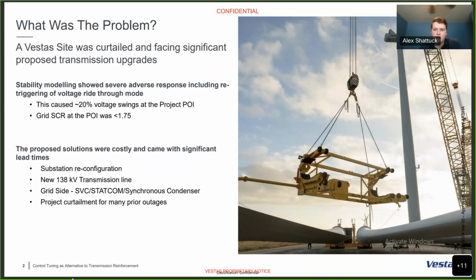The worst case, which no generator owner wants to see, is project curtailment. Basically, for any prior outage, any first level contingency that would cause the N-1/N-1 or cause the adverse response, they're going to curtail you significantly, and those prior outages could happen a lot. So you've just gone through the process, interconnected your plant, and now the ISO says you can't put all those megawatts on the grid, you have to operate at a curtailed amount, which would be a pretty terrible business case for any generator owner.